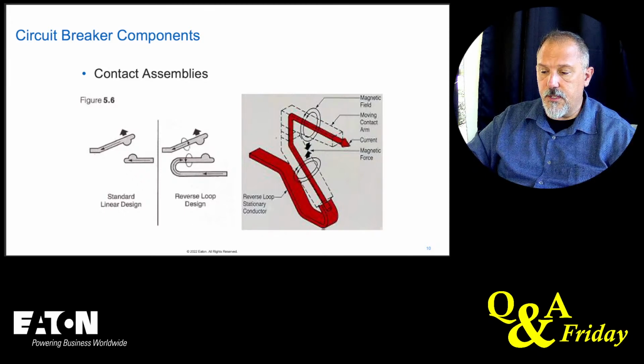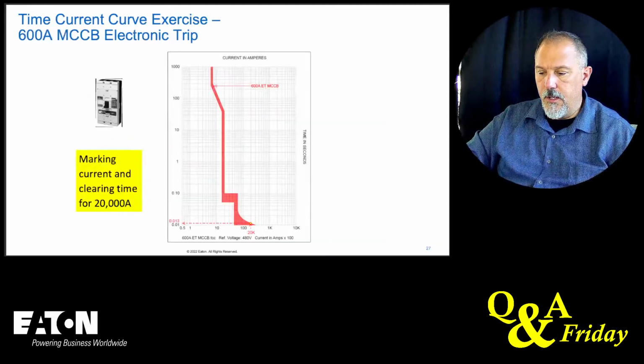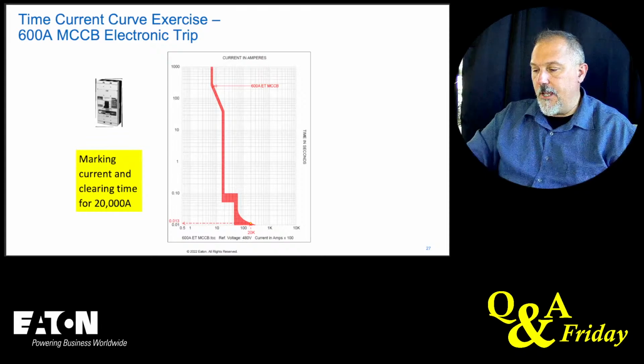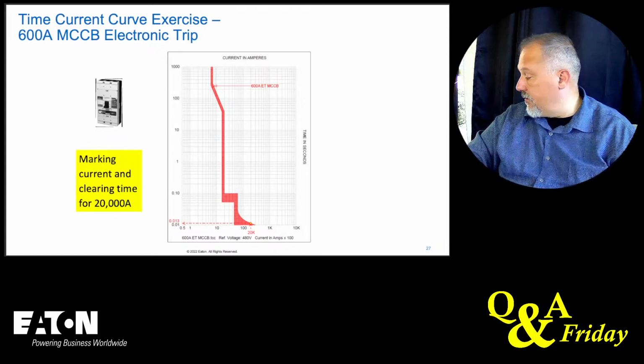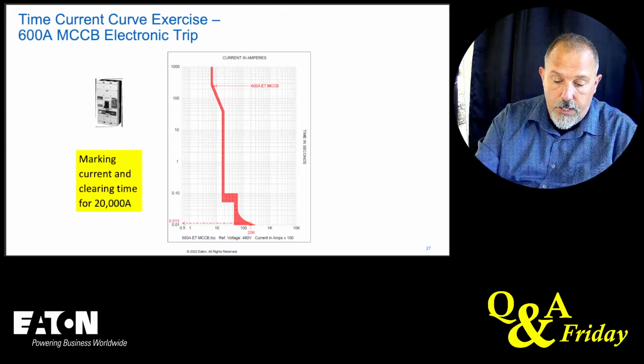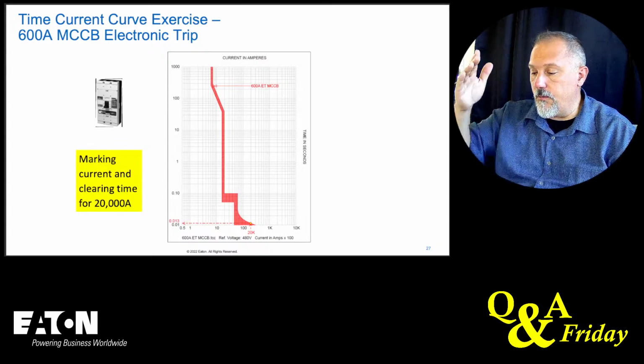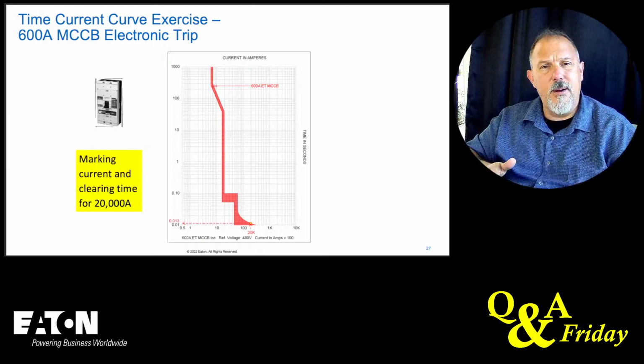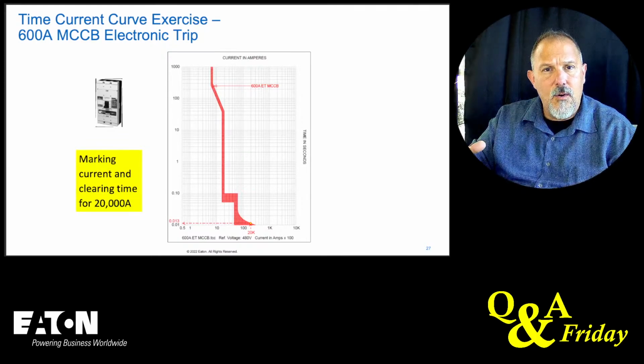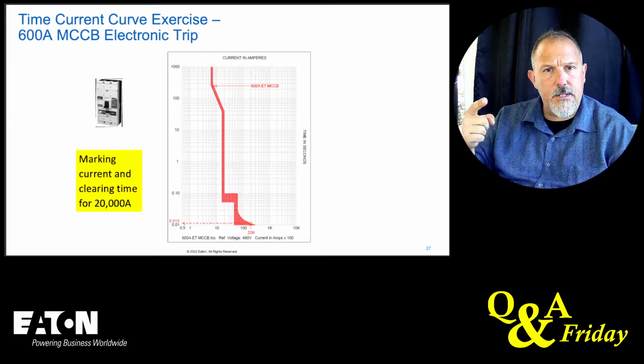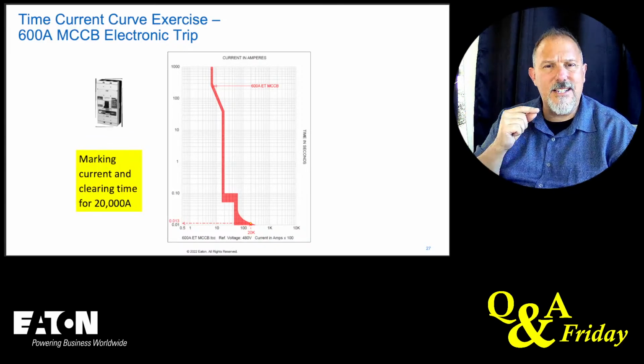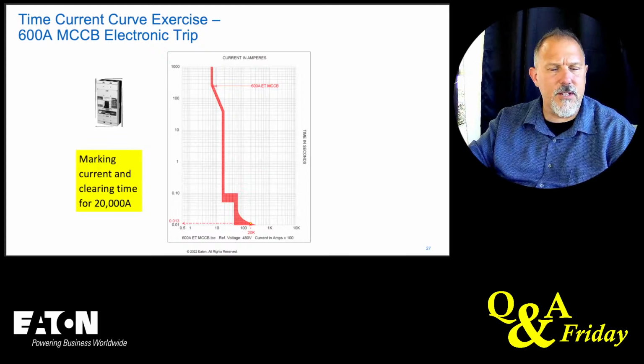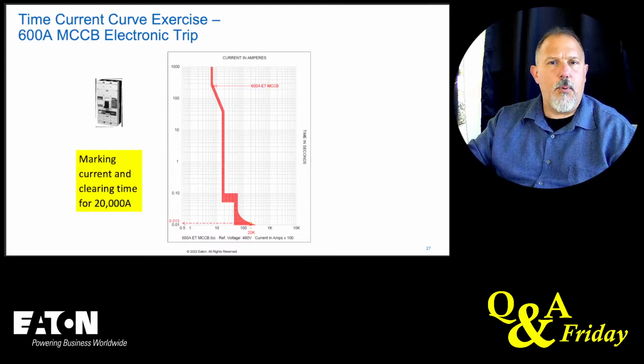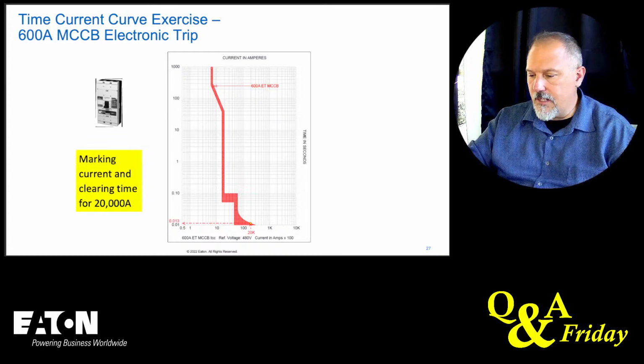So here we're going to look at, I think it's an 800 amp, 600 amp. So here's a 600 amp molded case circuit breaker. Now you'll notice that above a certain value down here on the right, we are faster. That's 0.01 seconds right down there at the bottom. What did we say one cycle is? One cycle is 1/60th of a second, 0.0167 or something like that, right? So say 0.016 seconds. That says 0.01 seconds clearing time in that instantaneous region.